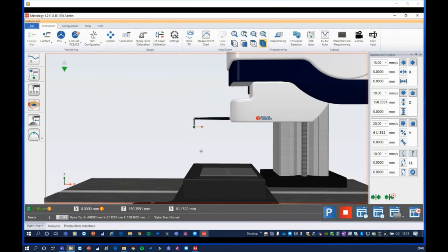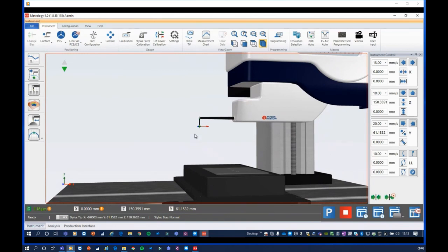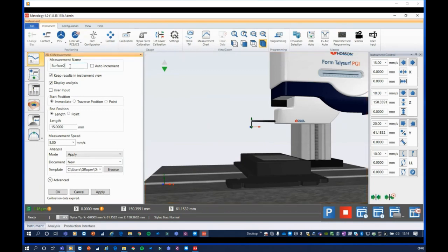So you saw in the video that we were actually loading against a model, and those points can be related to positions on that model. But I know exactly where that stylus tip is, I know exactly where that physical measurement is. And so now I know exactly where everything is. I can start to just use the visual instrument, the virtual instrument, and I will stop looking at the actual physical instrument. So again, I can go in here and let's create a surface 3.